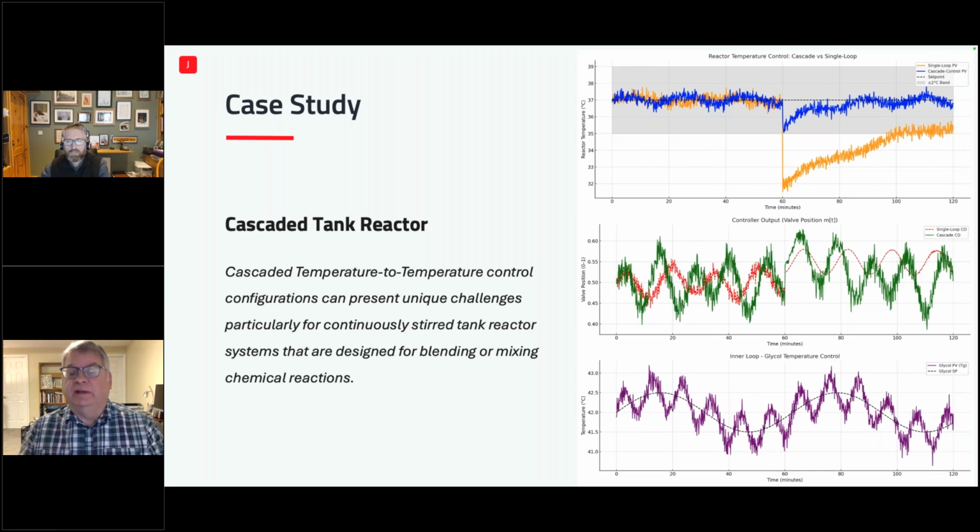And so to demonstrate that we have disturbance rejection, the blue line at the top of that, the second hour, if you will, that I captured, shows that we did have an impact from the disturbance, but my primary loop controller is also responding. So it is bringing me back to set point, and I didn't exceed my threshold. It's a factor of 2.5 smaller with the cascade control on it, disturbance rejection. It stayed inside your 2 degrees compared to the previous. The yellow is 5 degrees plus, so that's significant.